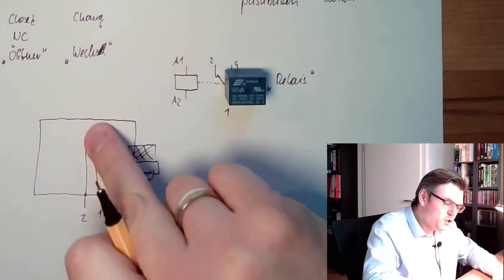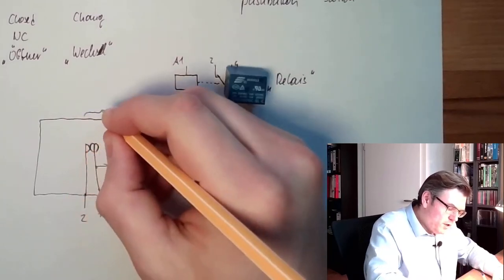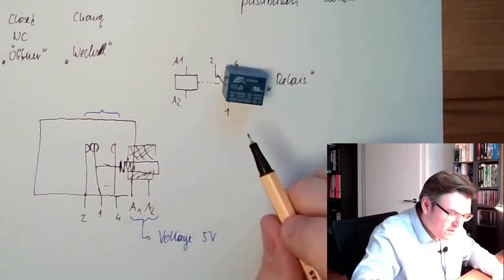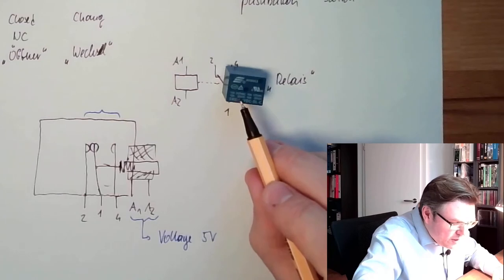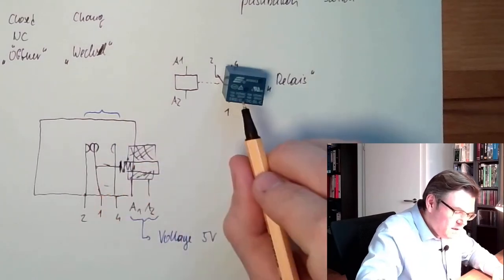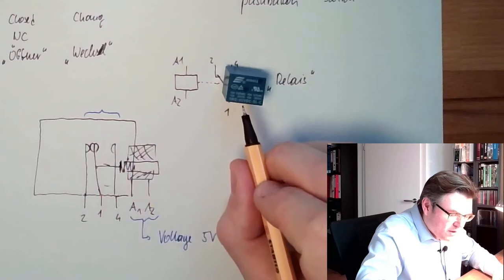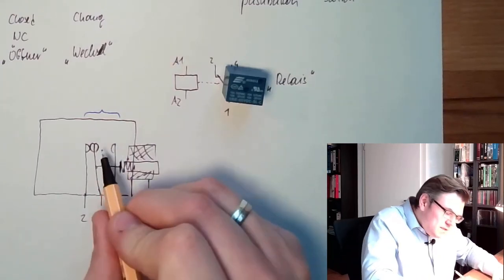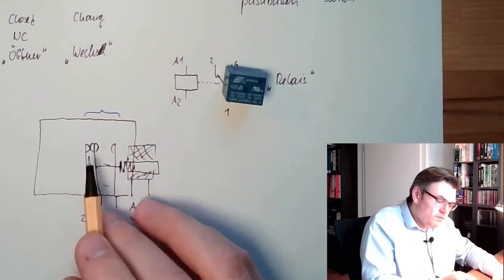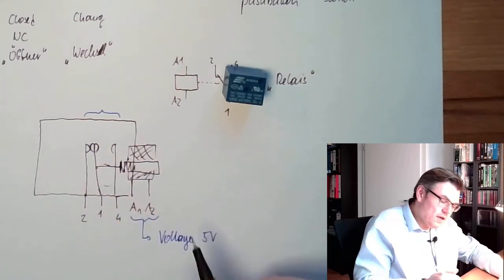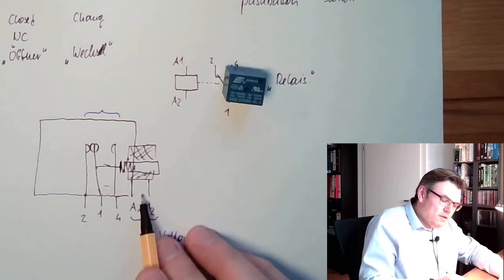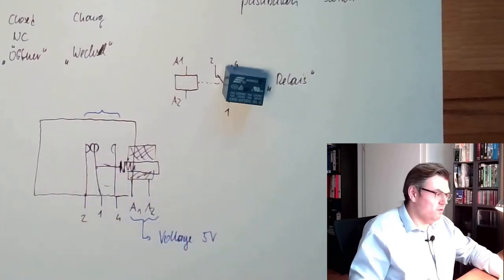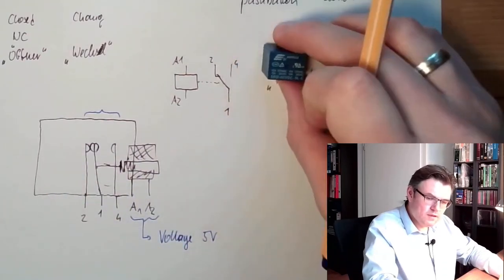And then there is the switching capability — how much power those contacts may switch: how much voltage and current. We can switch 250V AC and 10 amperes in this one, or 30V DC and also 10 amperes. This is the capability of the contacts. So there are two different things: the nominal voltage of the coil, and the capability of the contacts.